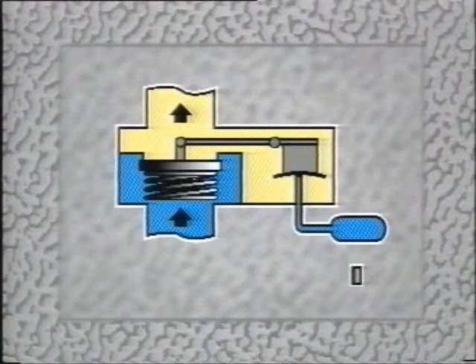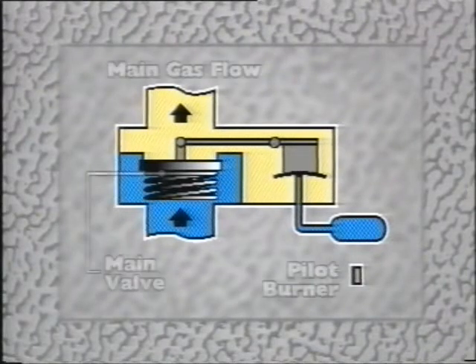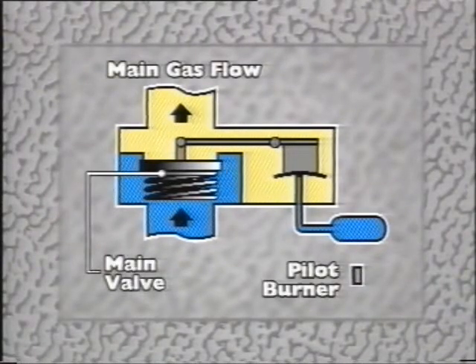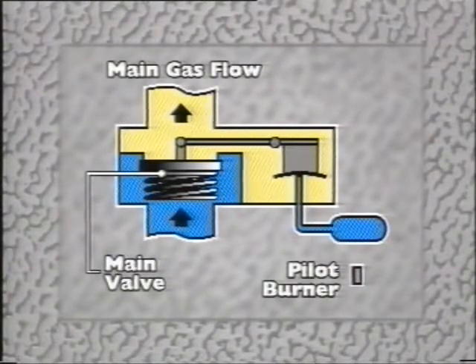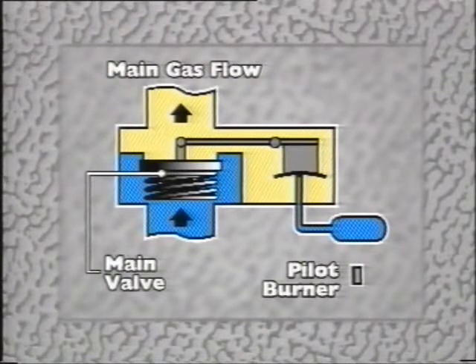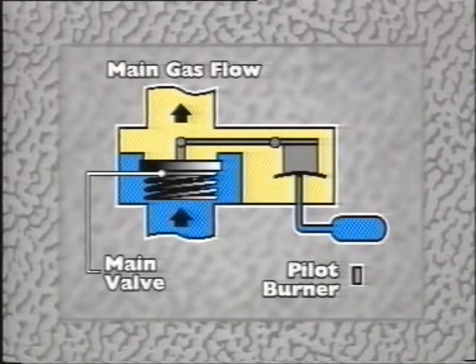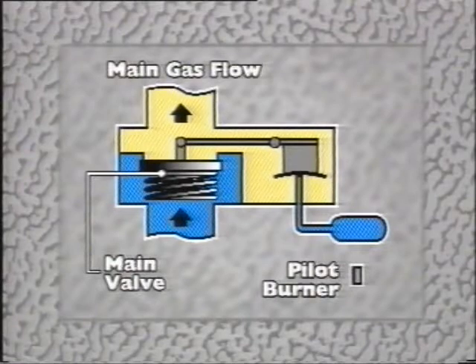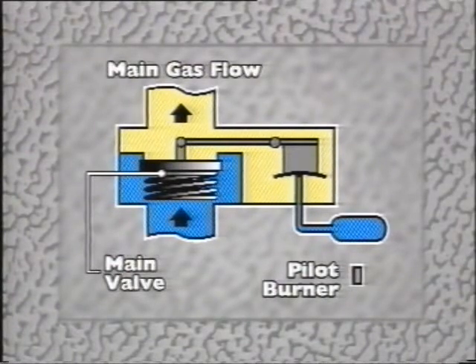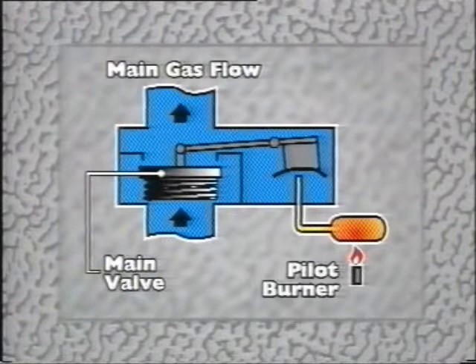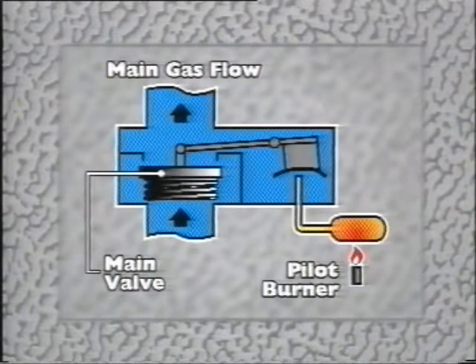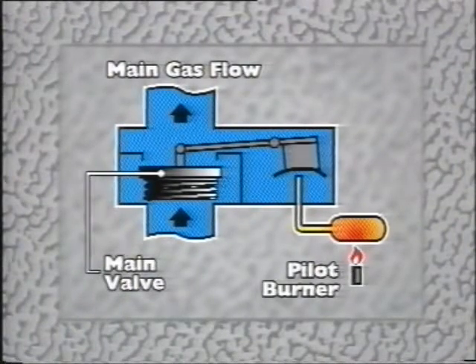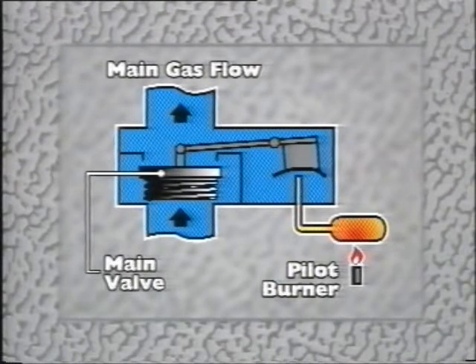The flame safety device lights the burner in 2 stages. First, a small gas flow heats the phial. This vaporizes the liquid in the capillary. It expands and so opens the main valve. The small flame then ignites the main gas flow. The flame safety device makes sure that the main gas can't flow unless there's a flame to ignite it.